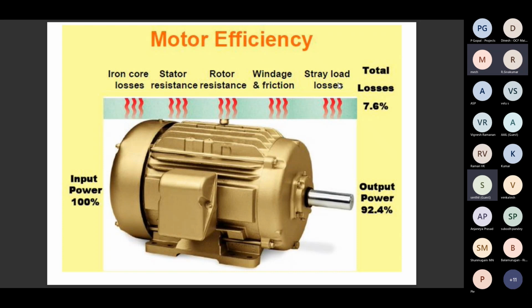Whereas the pumps used for the induction furnaces in the cooling tower run continuously, 24 hours in most of the foundry industry. So those pump motors can be installed with IE3 and IE4 because the running hours are very high, so the energy saving is very high compared to the investment cost. So the payback period is very short. Based on the needs and the application, the foundry, maintenance team and purchase team can decide whether to go for IE2, IE3 or IE4. Based on the operations, we can select. Next.